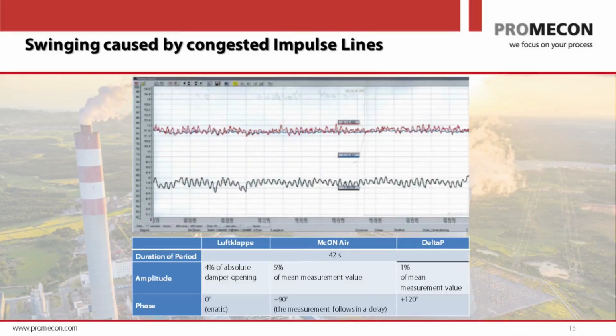Why do we have noise when the impulse lines get clogged up? We have this noise because some of the impulse lines are very long. They go over many feet from one burner deck to the other where all the DP measurements are lined up. And if you have such a long impulse line, then the change in delta pressure in a blocked impulse line will be transmitted very slowly. And you can see this very nicely when you have an analysis of the damper opening and the delta P. Those more or less sine waves that you can see are offset by nearly 90 degrees. So they are in perfect resonance condition. And as soon as you clean the impulse line, this is gone, and also the drift is gone. So that is the biggest problem. You do not have a stable and a drift stable signal.